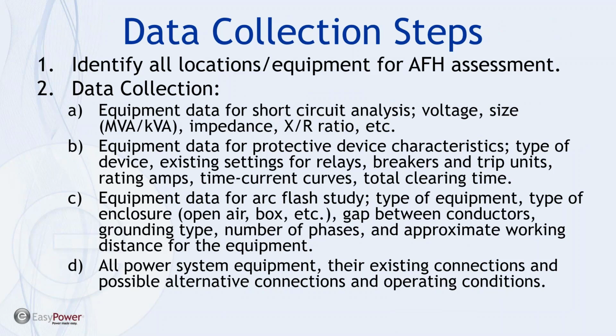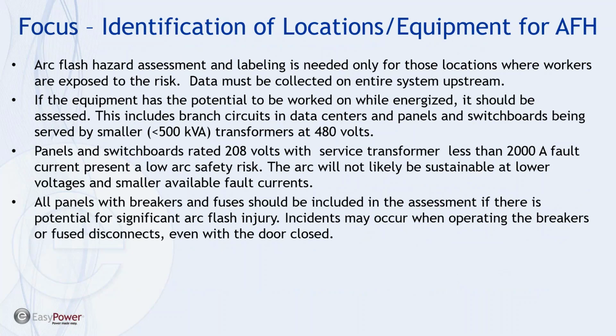So as I mentioned, have a plan of attack on how to do the assessment data collection by section. And while you're doing that collection, make sure you're capturing as much detail in the data on each piece of equipment. Frankly, anything in the medium voltage or higher voltage distribution system is more important than some of the panel information schedules down in the last leg of that distribution feeder. And frankly, the length of the cables is important, and that's probably one of the most difficult things to ascertain as you're collecting data on an older installation.